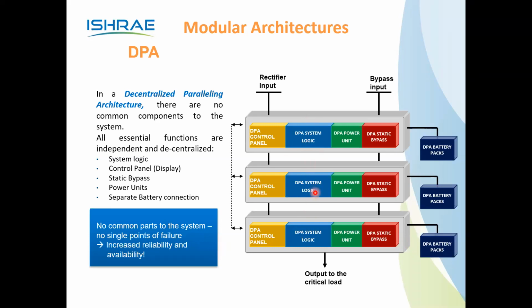Even if there is any problem, say the system logic fails, this particular module will not be in service, and the other two modules will support the load. Each module has a control panel with switches. This is another big advantage in this technology. In addition, modular UPS has the features of scalability as and when required, and serviceability, quick service support, and how friendly the support is. It's a DPA control panel. Each UPS has its own control panel and switches. With this technology, the customer need not worry about service support.